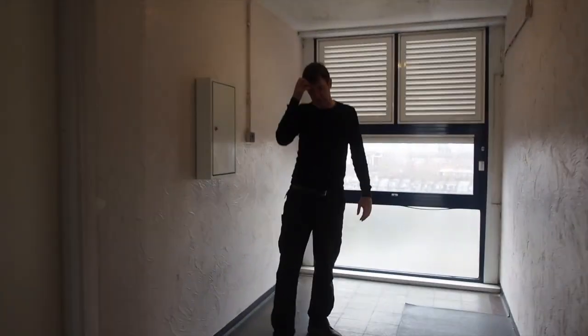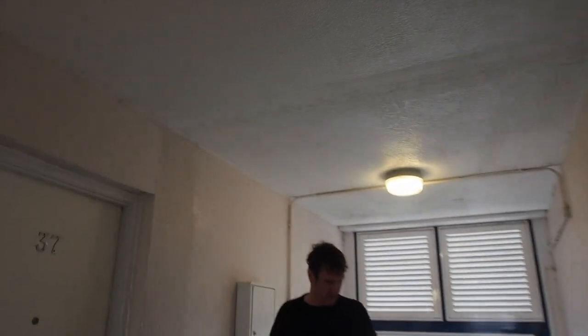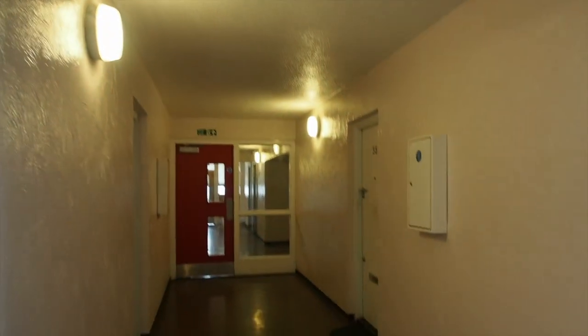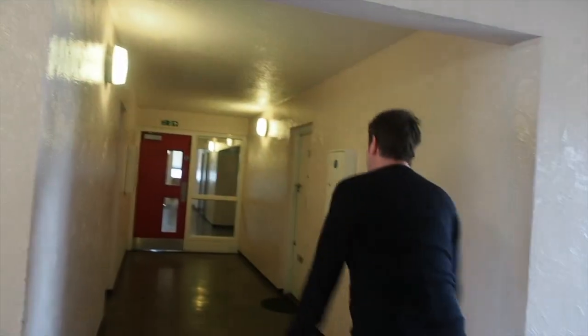Obviously, this was designed so that if someone comes in here and hangs their clothes up, this is going to air it nicely — it makes a very good drying room. However, some time ago they've removed this drying room, this laundry drying room. You can see it on the board, going down — this has happened on every floor, all three blocks of the estate. On the other side, you've got much smaller vents, and this hasn't changed — presumably because the designers didn't want too strong a draft. But now, having opened up the laundry room, you've got this huge draft moving from both sides and washing through here.